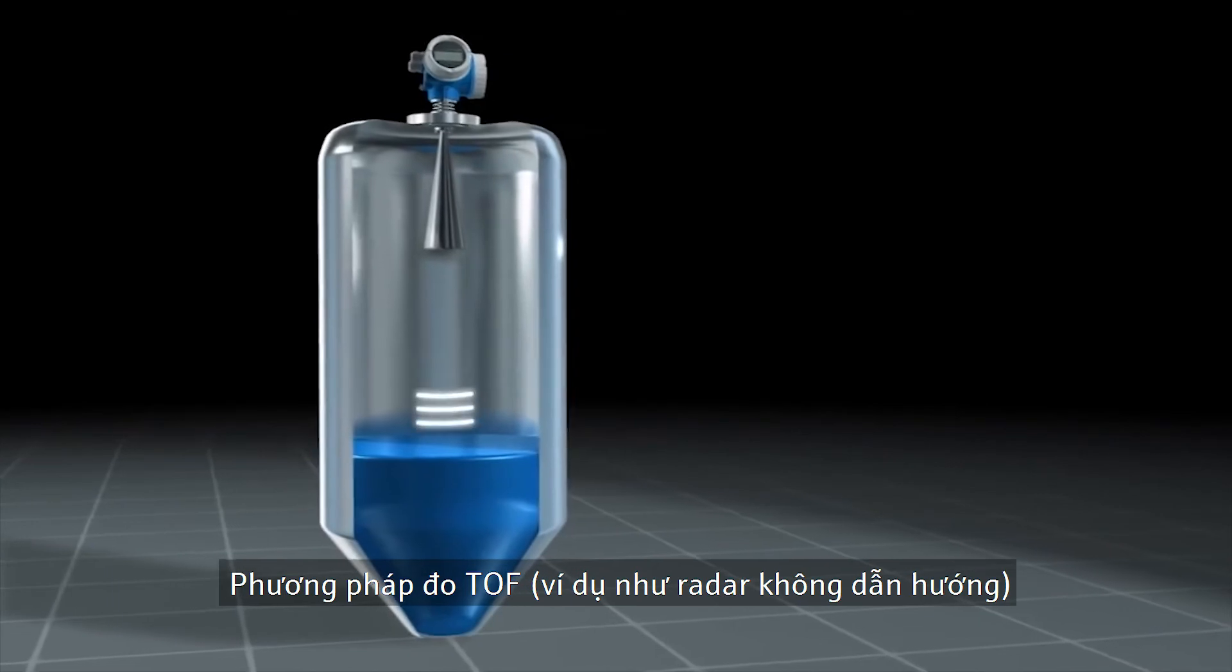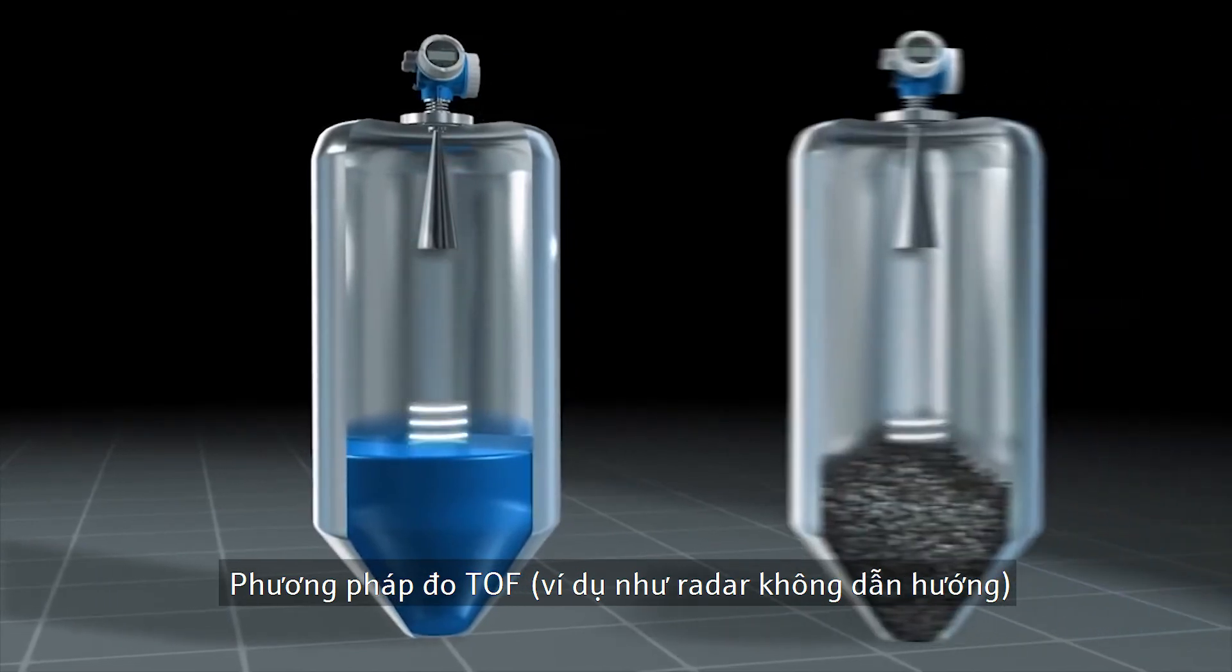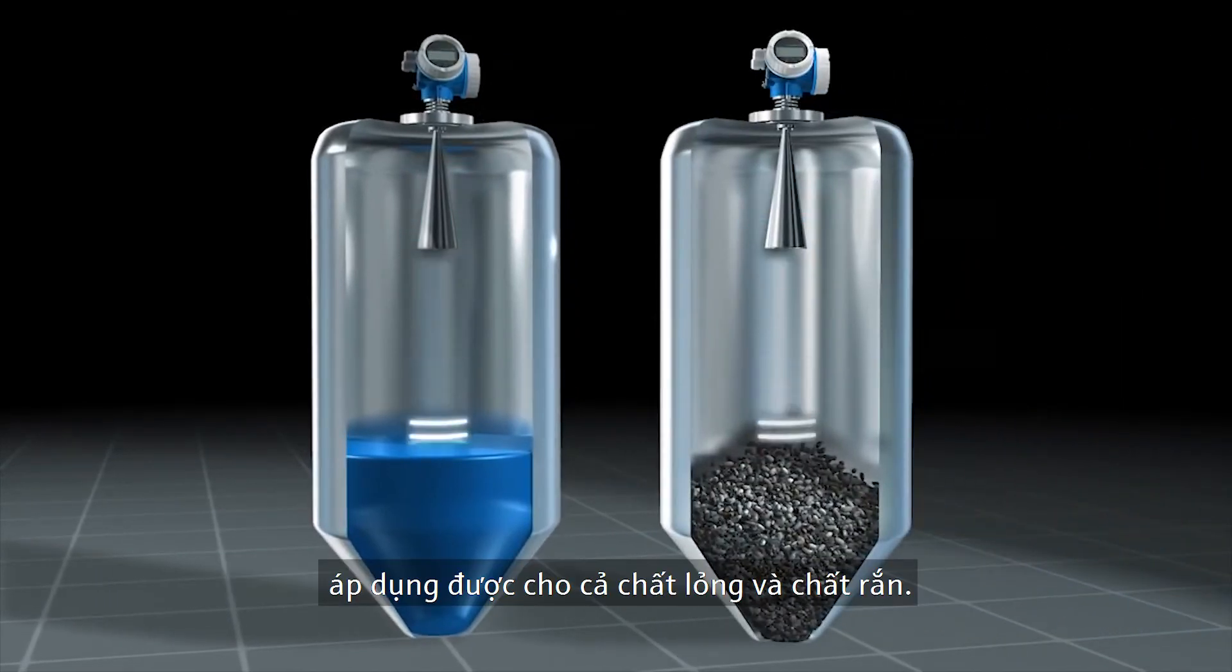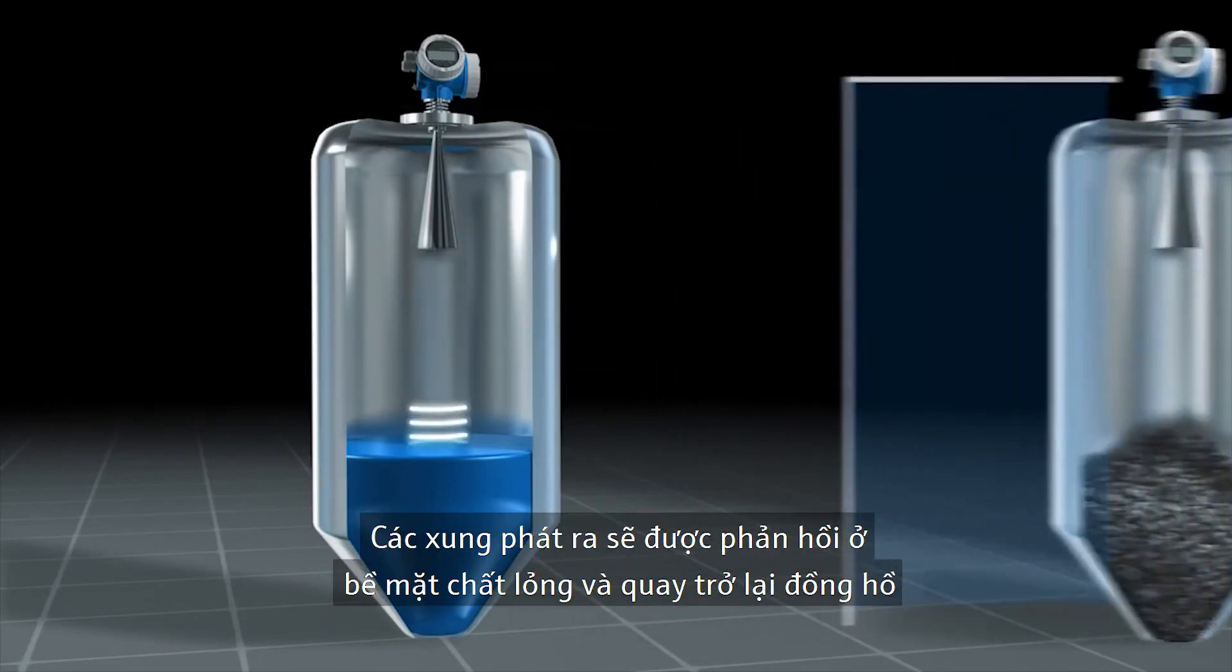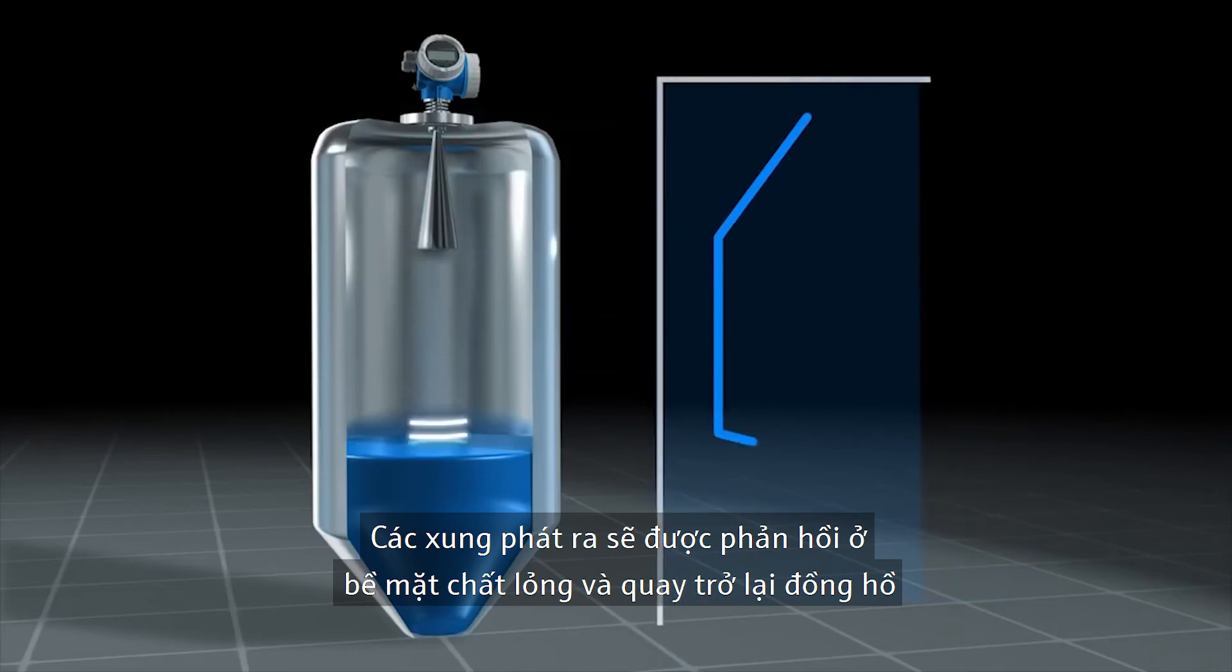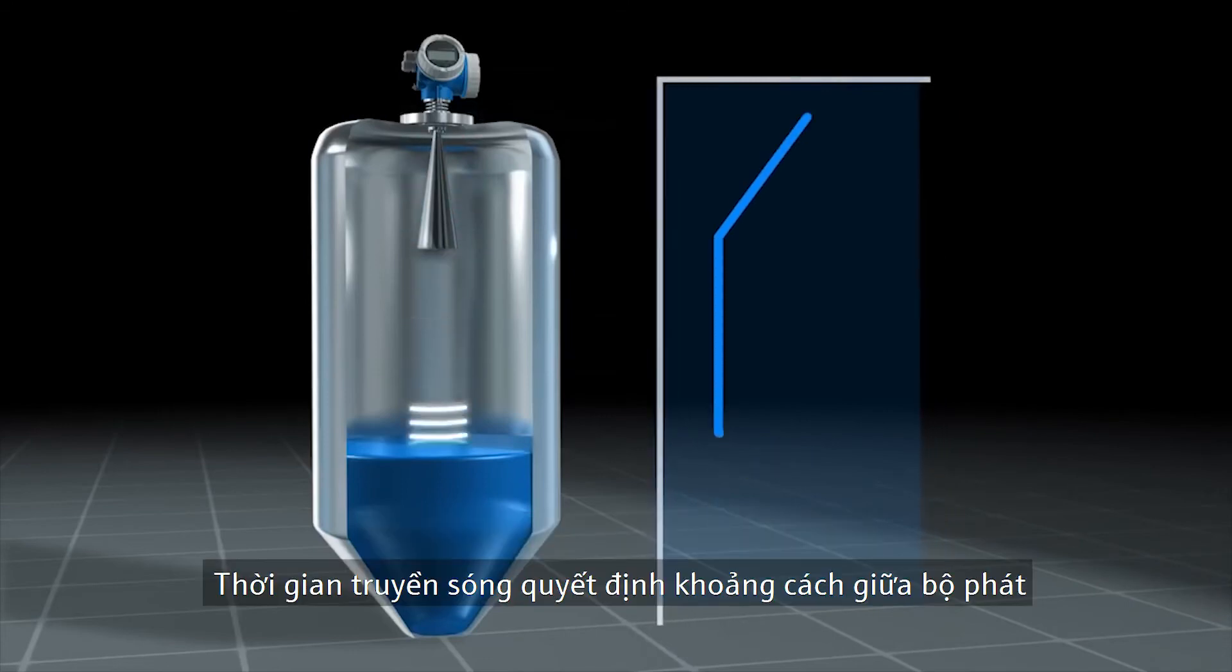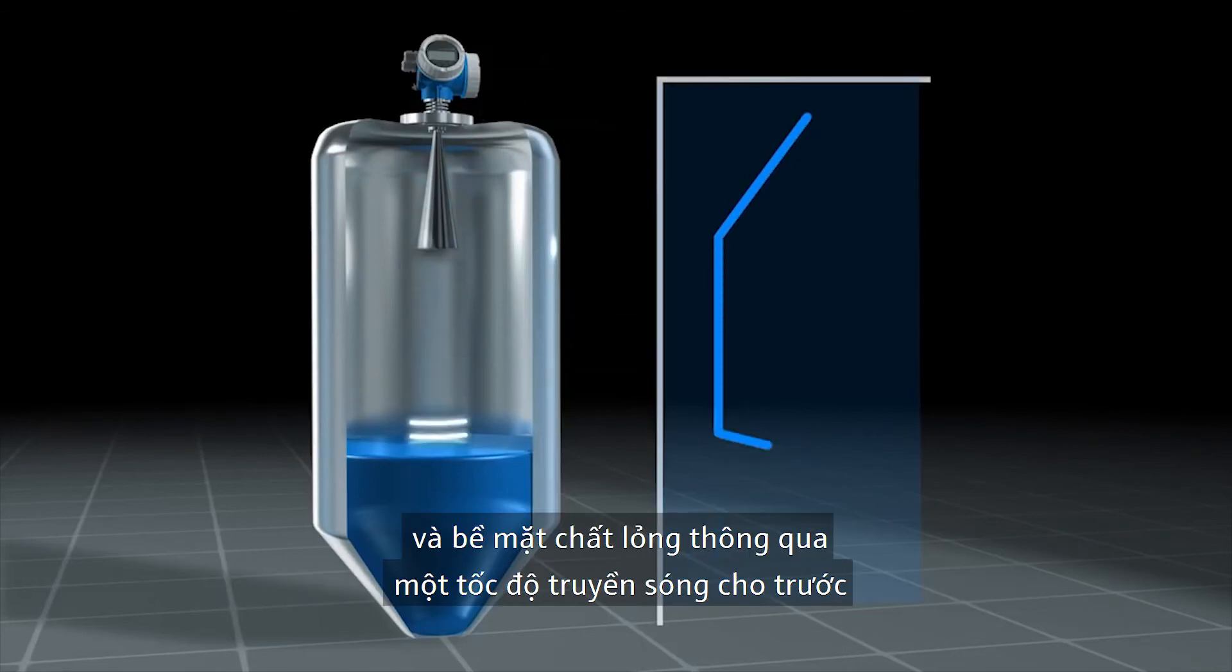The time of flight measurement demonstrated here by the example of free emitted radar pulses works both in liquids and solids. The emitted pulses are reflected from the medium surface and detected by the instrument. The time of flight of the pulse determines the distance between the transmitter and the surface using the known propagation speed.